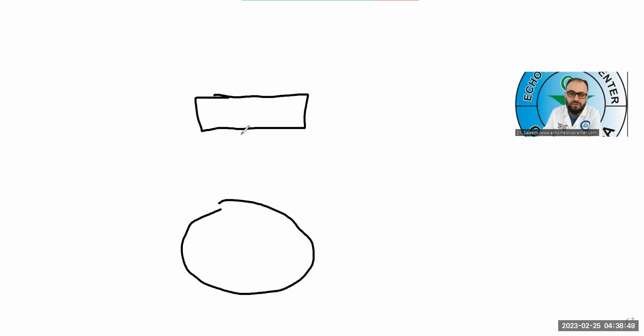It means like this. Let me show you here. For example, this was pulse number one. It just came to the bottom, to the floor of this urinary bladder. So they take information from the bottom of this floor. Now, this pulse is going back with the information, correct? So it comes here. Now, the second pulse fired ahead of time. This blue one, the reflection, is supposed to go all the way to the receiver, and then the next one will fire. But the second pulse just fired prematurely, ahead of time.